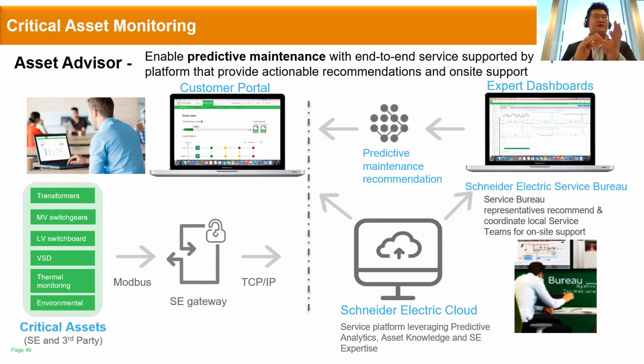It's just like having a crystal ball - that crystal ball is this kind of asset advisor. It can monitor any defects, for example in a transformer, partial discharge. It is a signal for the problem - when partial discharge happens, it shows there are electrical problems in the transformer that will cause it to fail very soon, leading to an unexpected shutdown.